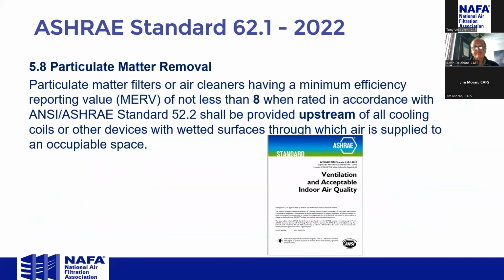Okay. So one thing that got me really interested during the pandemic was the ASHRAE standard 62.1 2019 at the time, but now 2022. And if you read this, it still is recommending a MERV of not less than 8 when rated in accordance with ASHRAE standard 52.2. So 10 years after we first developed the NAFA guideline for commercial office spaces, we were recommending a MERV 13 at that time. We still recommend MERV 13 or better. And unfortunately, ASHRAE is still at MERV 8, though I'm pretty sure. Next slide, Tony.